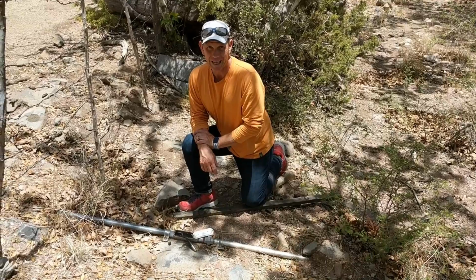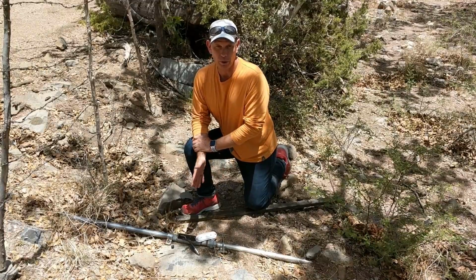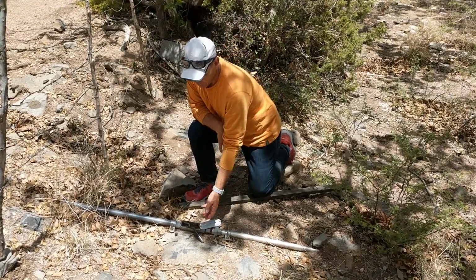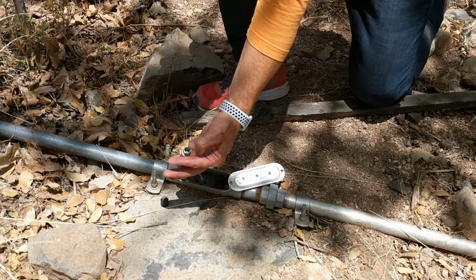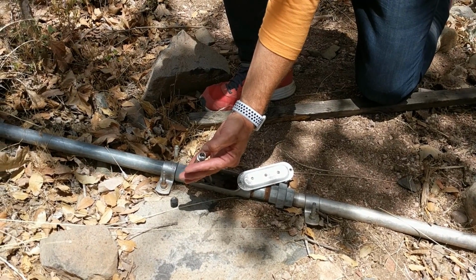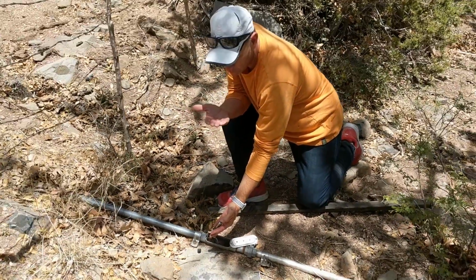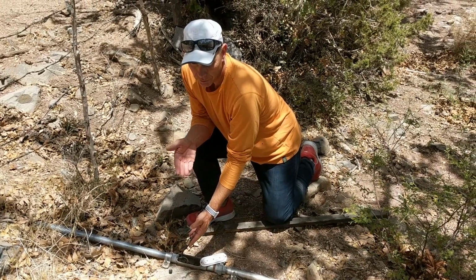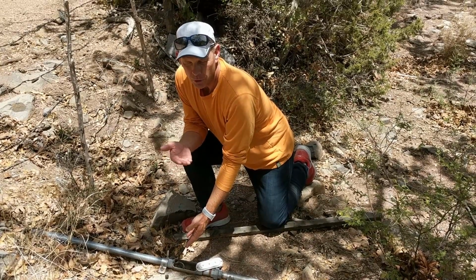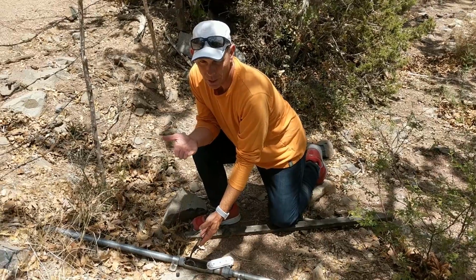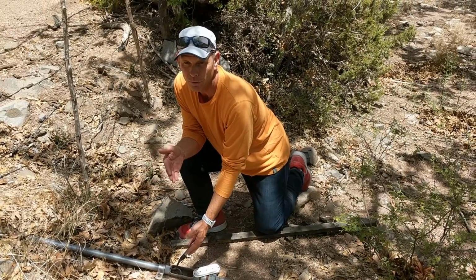So here at Sycamore Creek, as at most of our stream gauges, the level is measured with a pressure transducer. And we have one here that I'm going to demonstrate for you. I took the cap off, which goes here, and inside there's a diaphragm. As water hits the diaphragm, that's when pressure goes against it, and it begins to show the water level rise as it's going up. With a calibration, it knows when 1 foot of water is here due to the pressure differences. As it continues to rise, the pressure increases, and our system knows how to convert that into actual feet of water level.